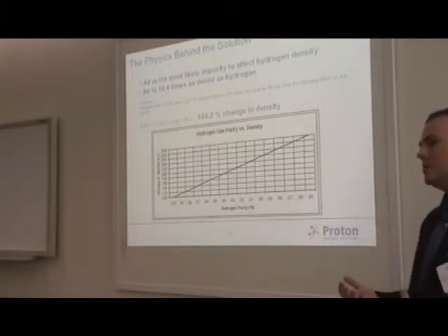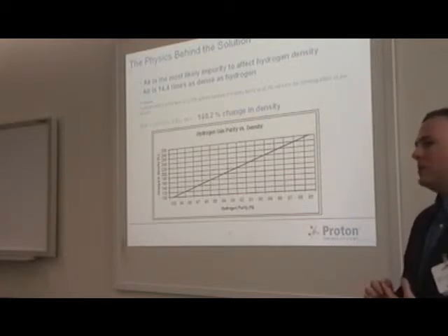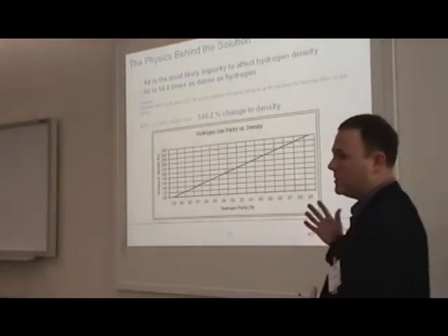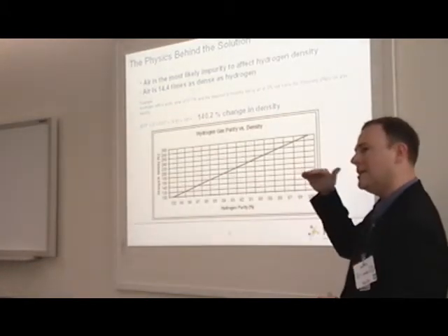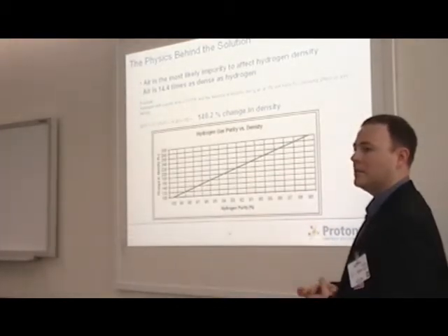So the basis for using hydrogen electric generators is, number one, hydrogen is an outstanding conductor compared to air, and it's much less dense than air. So by maintaining a high purity in the electric generator cavity, you're minimizing windage losses. And that minimization means you're burning less fuel for the same amount of power output, or you can burn a little bit more fuel for a little bit more power output, depending on how your plant's configured and what the limitations are on the rest of the plant. And that's what stable flow is designed specifically to do, to bring those electric generators that are out there at maybe 95%, 96%, or 93% hydrogen purity, to bring those up to 99%. So that you're minimizing the energy in to the spinning of the electric generator and maximizing the electricity out.